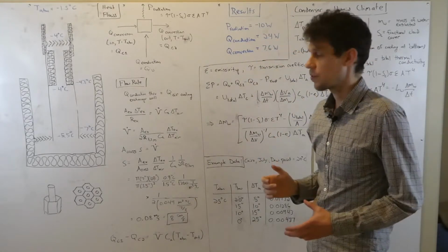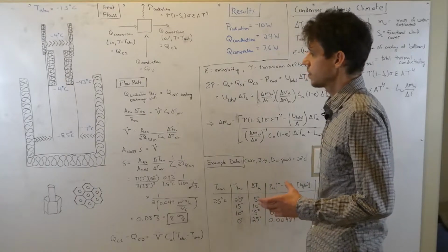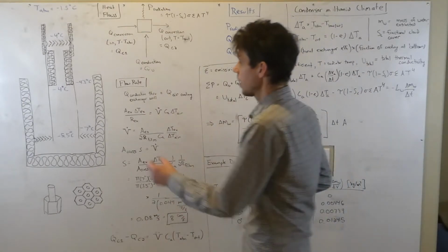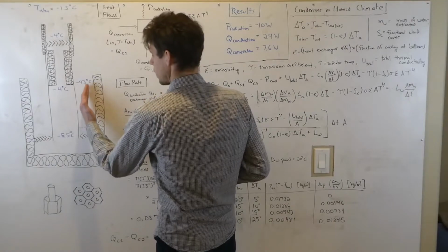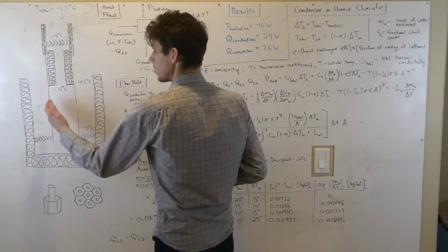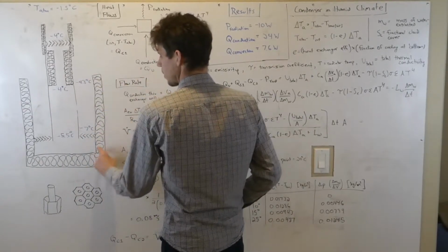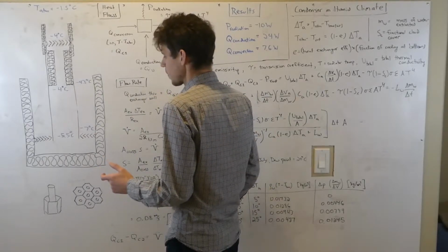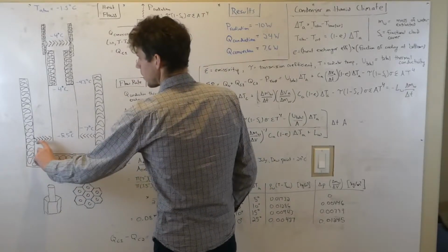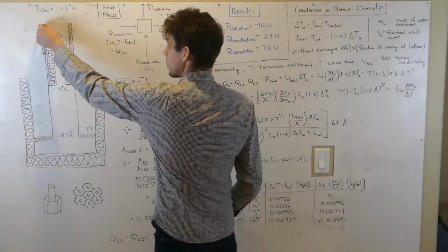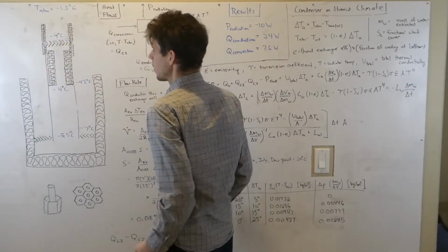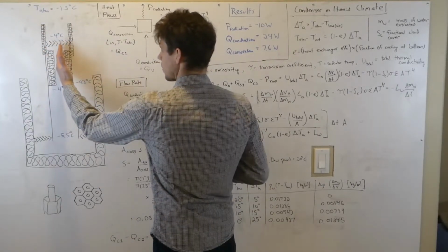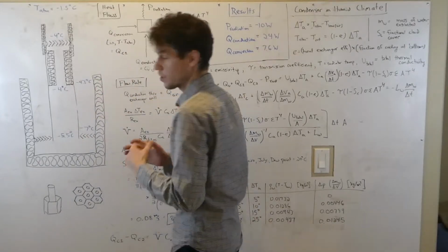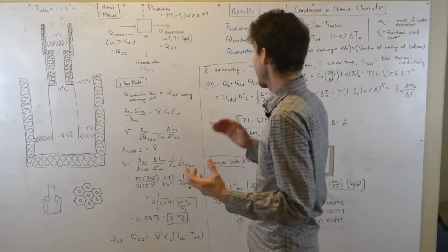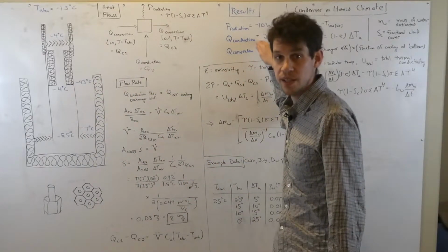I also solved for the conduction just with formulas. I figured out the temperature difference between this column and the outside on average, then used the R value of our fiberglass insulation, the R value of the foam on the bottom, and the R value of the insulation on top, along with the differences in temperatures between these air streams and the outside, to directly solve for the conduction—and it was really, really close to the other method.